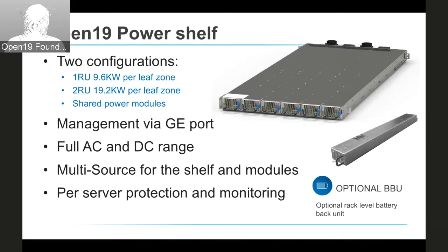The other thing for this, we have a dual BMC module inside, two CPUs which are running a Linux environment, which will be open source running OpenBMC, and will enable you to actually, if you need to, write a management system into that PowerShelf, write code into the PowerShelf itself, or connect to an API that will be defined in the future for the shelf to enable your management system to monitor, control, and drive the PowerShelf from the outside.